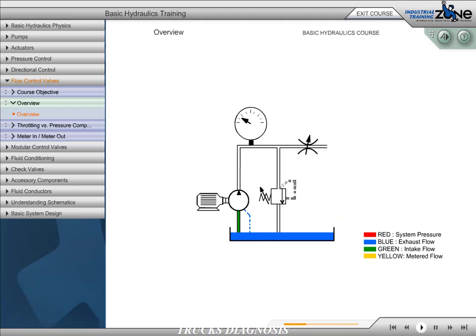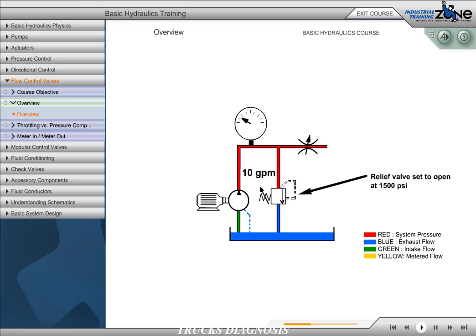This circuit uses a fixed-volume pump. To reduce flow to the actuator, we must bypass a portion of the fluid over the relief valve. As we close the needle valve, pressure increases upstream. As we approach 1500 PSI, the relief valve begins to open, bypassing a portion of fluid to the reservoir.